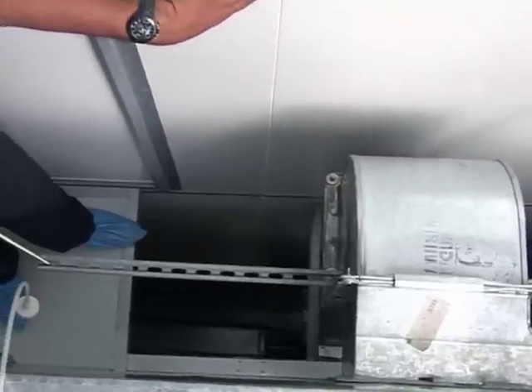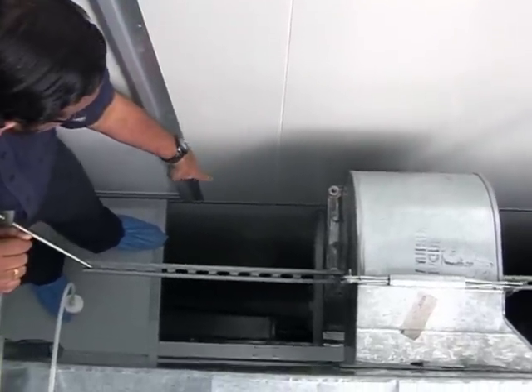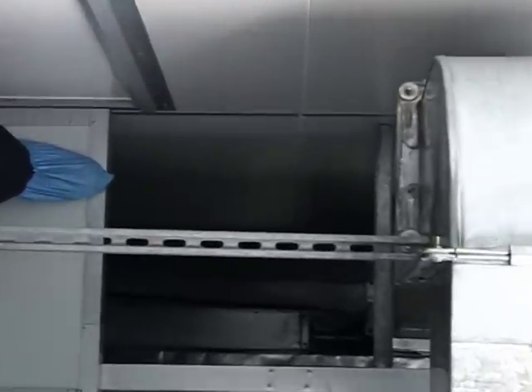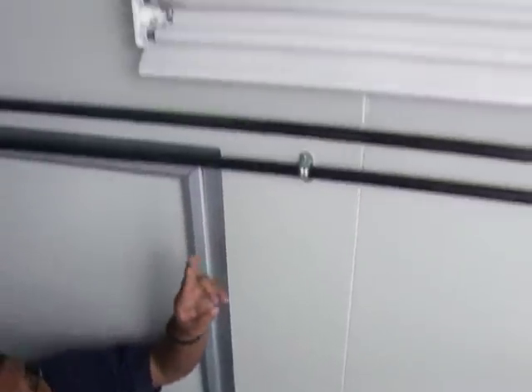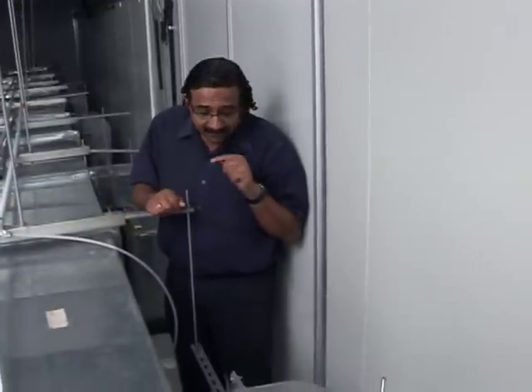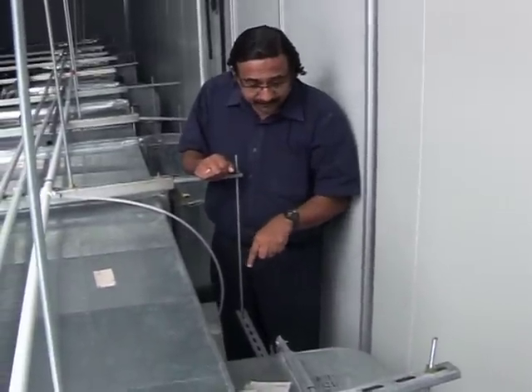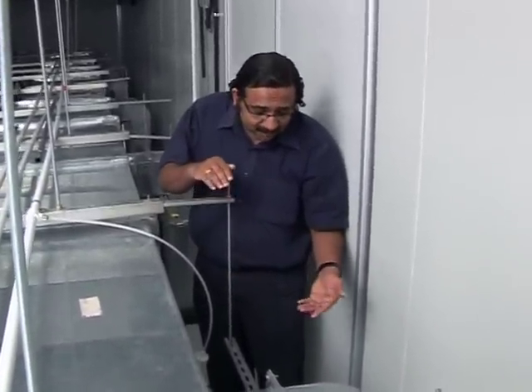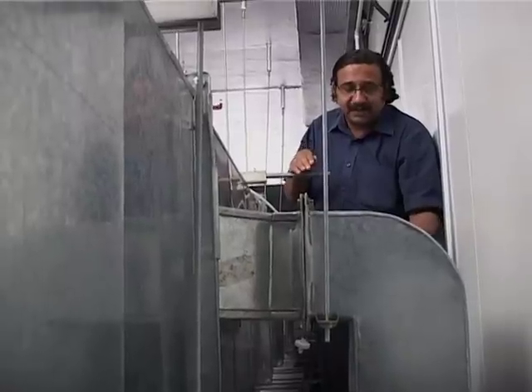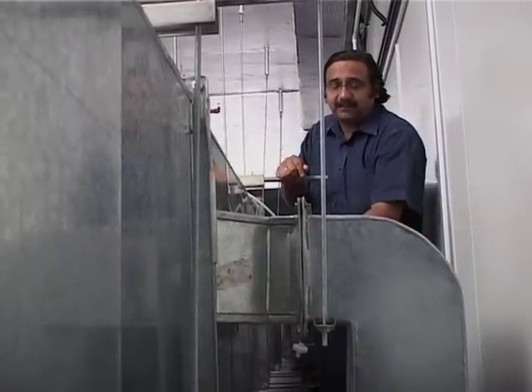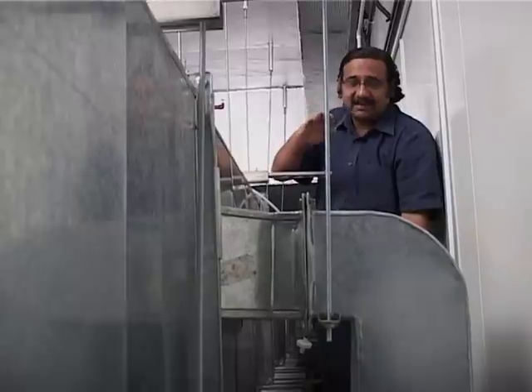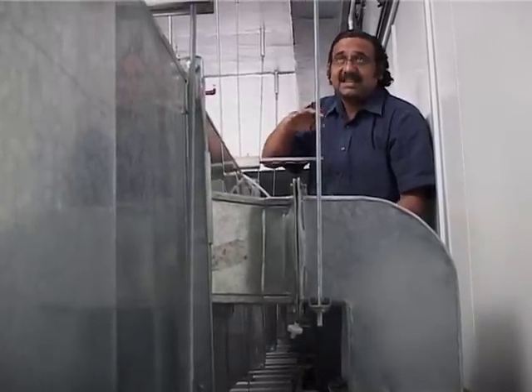This outer wall starts from the bottom of the basement area to the top of the plenum area. So this is a very long panel. Now we have an inner panel that starts from the bottom, or the floor, of the clean room area and ends at the roof, that is, the beginning of the plenum area. So that is a relatively shorter panel that defines the height of the clean room.